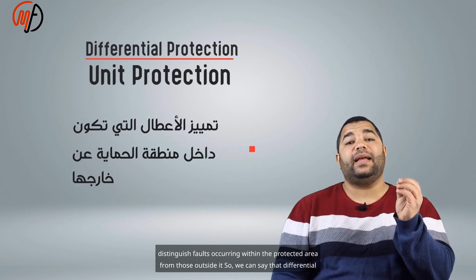Differential protection is considered one form of unit protection, characterized by its ability to distinguish faults occurring within the protected area from those outside it. So we can say that differential protection is unit protection, but we cannot say that all unit protection is differential protection. One of the other forms relies on pilot protection lines.